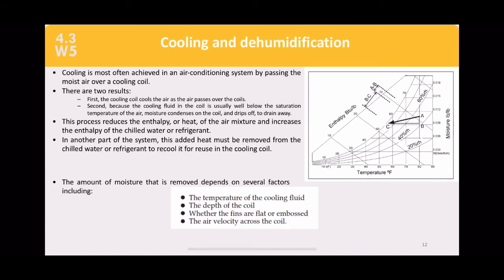Next is cooling and dehumidification. Cooling in an air conditioning system is achieved by passing moist air over a cooling coil, which absorbs heat and cools the air. Because the cooling fluid is well below the saturation temperature of the air, moisture condenses on the coil and drains away — removing heat by both absorbing heat into the coil and condensing water vapor into liquid.